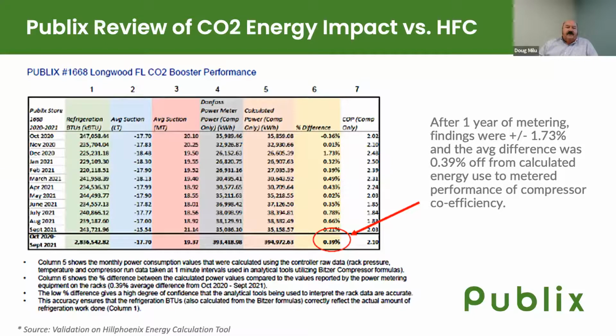Yeah, so this chart, it's a bit of an eye chart, and I apologize. However, this was a study that we did at our Longwood store. This was our first CO2 transcritical installation. And we compared this to a traditional HFC store with similar systems, similar MBTU for the low temp and medium temp systems. We worked with our systems manufacturer and our controls manufacturer. We sub-metered just about everything that we could within the machine house. And really this is regarding coefficient of performance for the compressors. There's a bit of an advantage there. If you've seen some of the CO2 compressors, you realize that they're much smaller in physical size because of the efficiencies of CO2. So it's no surprise that we got some really good compressor performance.